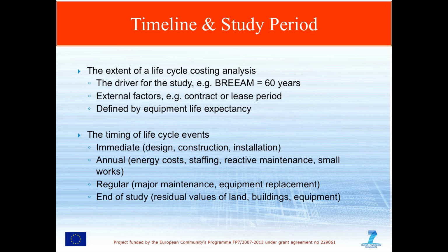Sometimes if you're looking at a very focused life cycle cost analysis, then you can try and link your study period to the life expectancy of the major pieces of equipment that you are going to be dealing with. That makes sense if you're only interested in the heating system, the cooling system, the lighting or whatever. Just analyse it for its life expectancy. There's quite a lot of information generically, but also that can be customised, to tell you what that sort of life expectancy might be, and he's already hinted at some of them in terms of the information that CIBSE produces.